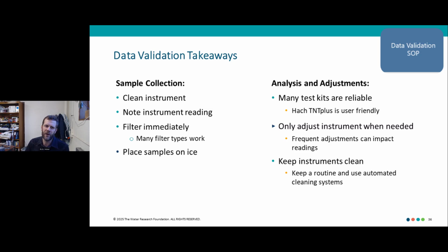The other part that we wanted to note was that for matrix adjustments, it's really important to only make those adjustments when they're needed and really pay attention to the overall trends, and not have a knee-jerk reaction if you have one sample that seems to be off by a little bit. We talked to several utilities and manufacturers, and what they said was that trying to overcompensate for a seemingly erroneous reading will lead to sensor drift and will lead to worse readings down the road.